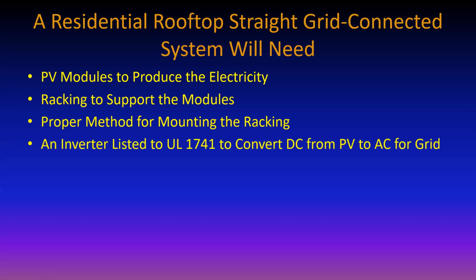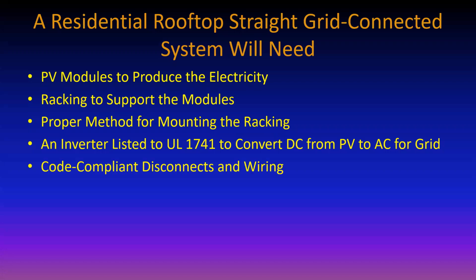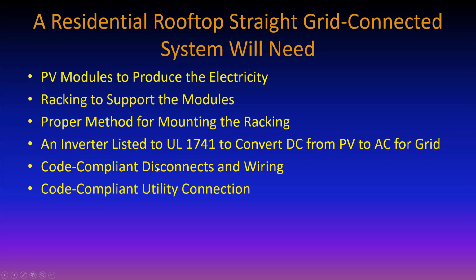We need an inverter listed to UL 1741, the UL testing standard to meet IEEE 1547. This inverter converts the DC from the photovoltaic array to grid quality or utility quality alternating current for the grid. We have a bunch of code compliant disconnects and wiring, but that's all in the National Electrical Code, various articles. 690 is the primary photovoltaic article, but then there's 705, and then you get back to 250 and so forth. We'll be listing a number of the specific National Electrical Code articles that we need to pay attention to. We need a code compliant utility connection, and that's generally in National Electrical Code section 705.12.